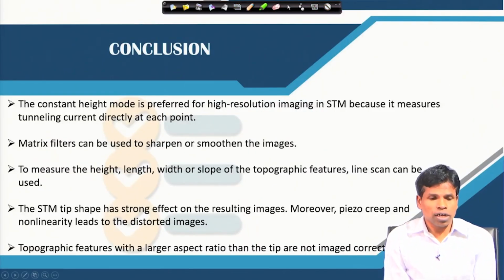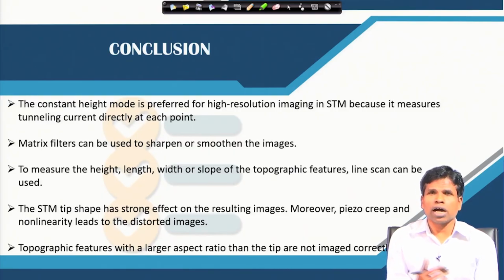So, in conclusion, constant height mode is preferred for high resolution STM images because it actually measures the current at that same place. Different types of matrix elements and filtering are used to smoothen the images to get a cleaner image, and to measure the length, width, height or thickness of the layers. The line scan can be utilized to get quantitative values.